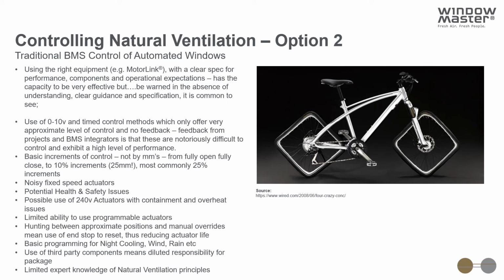Traditionally, there's an awful lot of different methods for BMSs to control automated natural ventilation. Use of 0 to 10 volt and time control methods quite often have very limited levels of performance. It's very much estimated, and it's difficult for the BMS to know where the vents are, so delivering accurate control of vents at small opening distances is very difficult to achieve. It's also very complex to program, meaning the BMS may elect to have much larger increments of control. Most commonly, we've seen 25% incremental opening, but as we saw earlier from the aerodynamic curve, 25% incremental opening could potentially introduce more problems than it solves, resulting in too high levels of ventilation, excessive drafts, and potentially a heating demand.